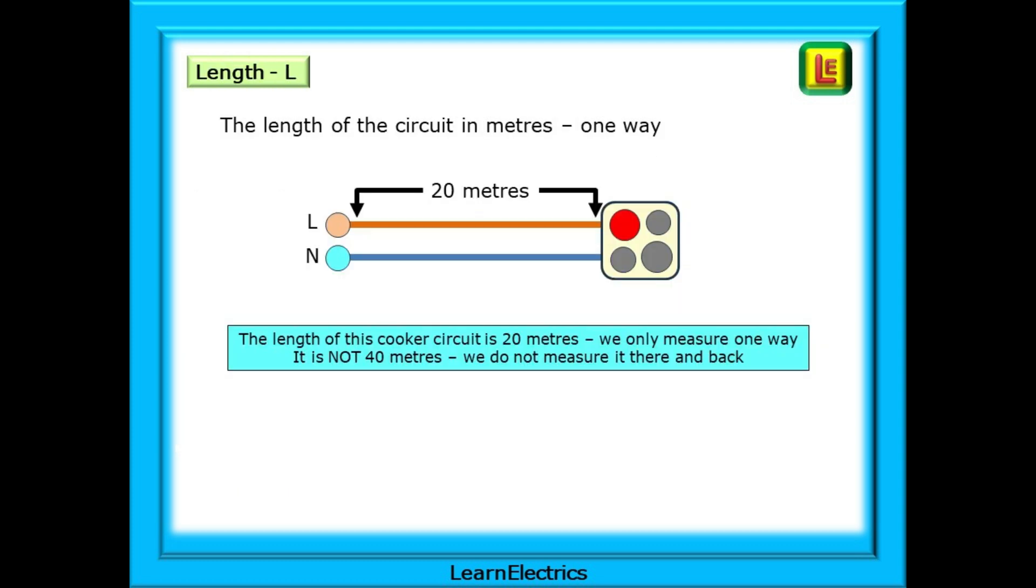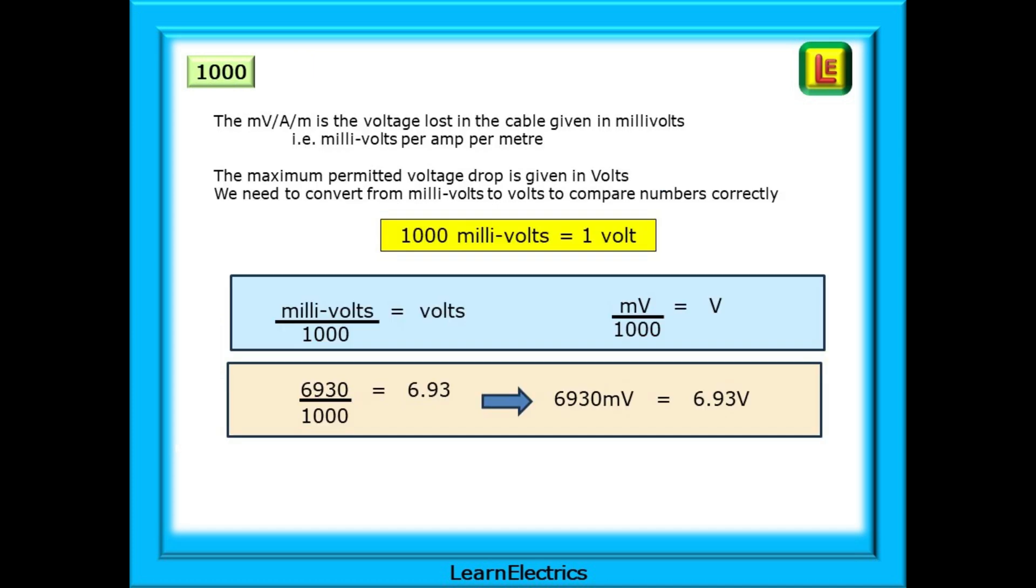Length is simply the meters from the consumer unit to the cooker. The length of this cooker circuit is 20 meters. We only measure one way. It is not 40 meters. We do not measure it there and back. The number 1000 matters. The MVAM number is the voltage lost in the cable given in millivolts. That is, millivolts per amp per meter. But the maximum permitted voltage drop is given in volts. We need to convert from millivolts to volts to compare numbers correctly. And we do this by dividing our answer by 1000. Shown here, our answer is 6930 millivolts. Divide this by 1000 to get 6.93 volts.